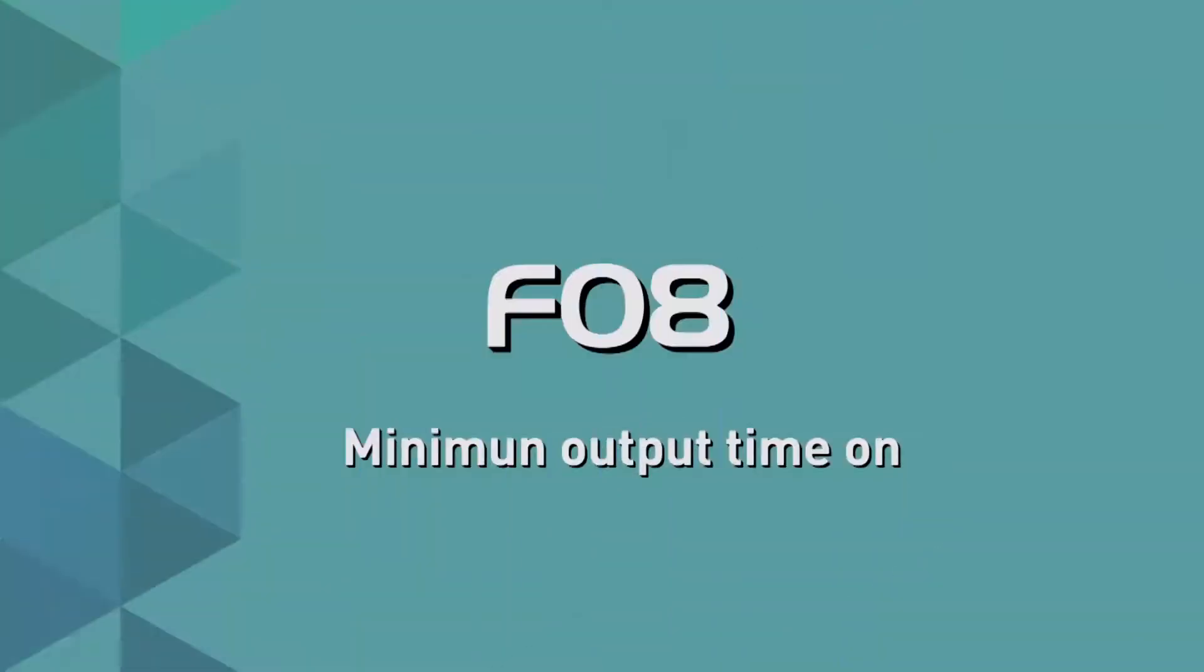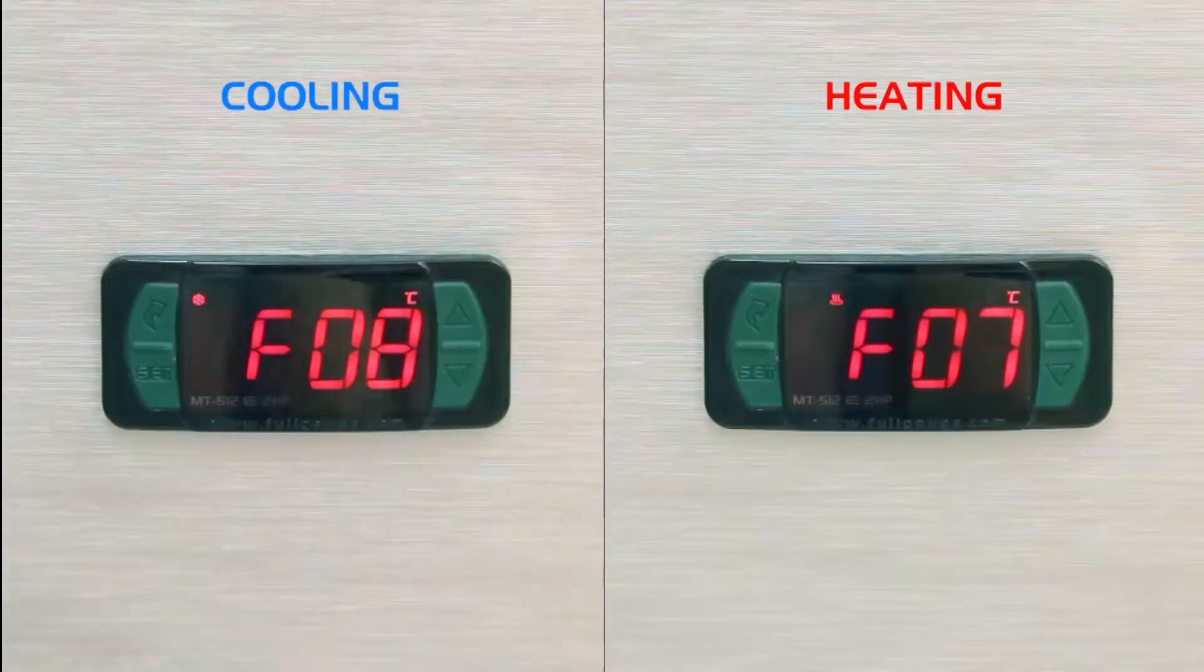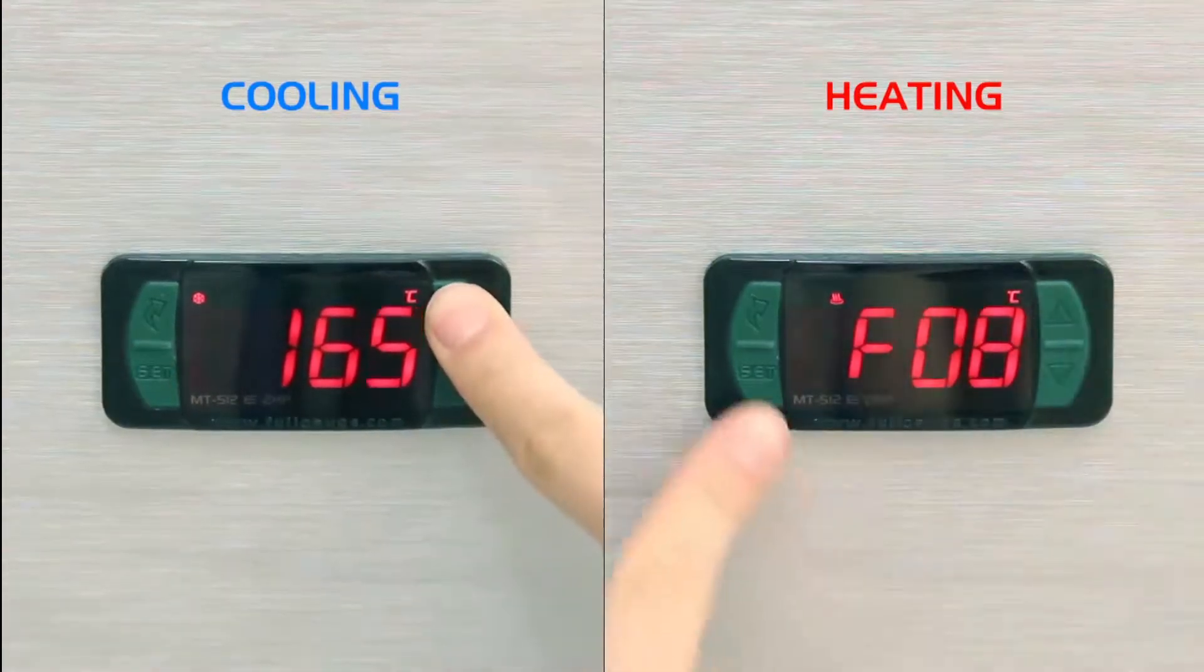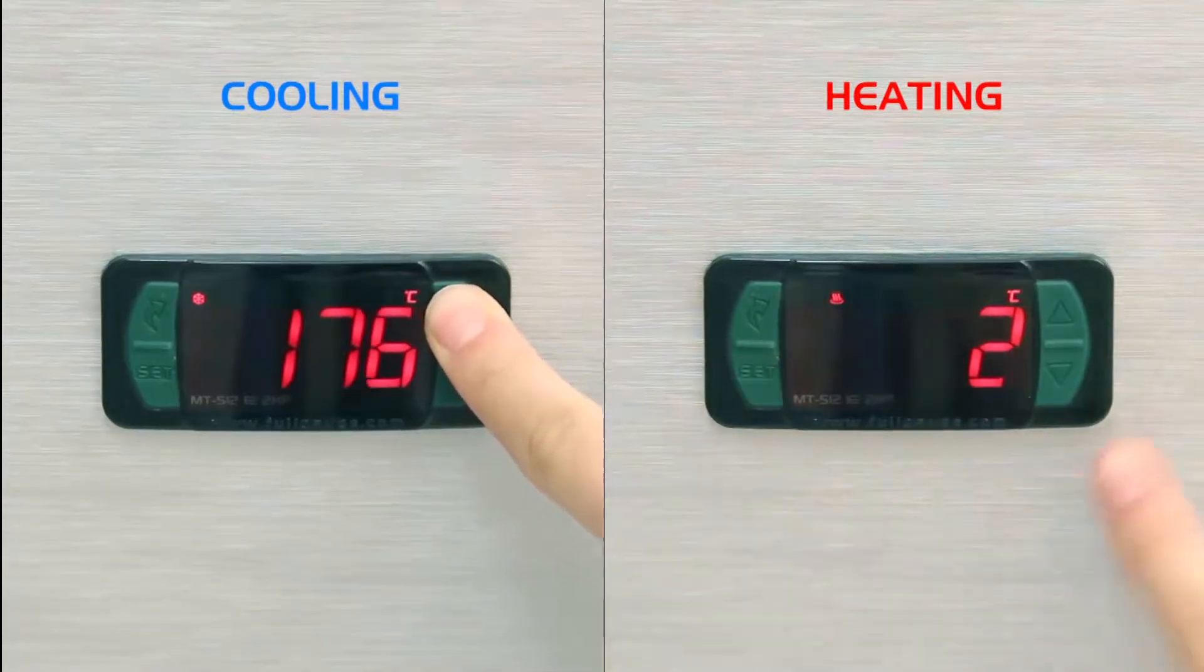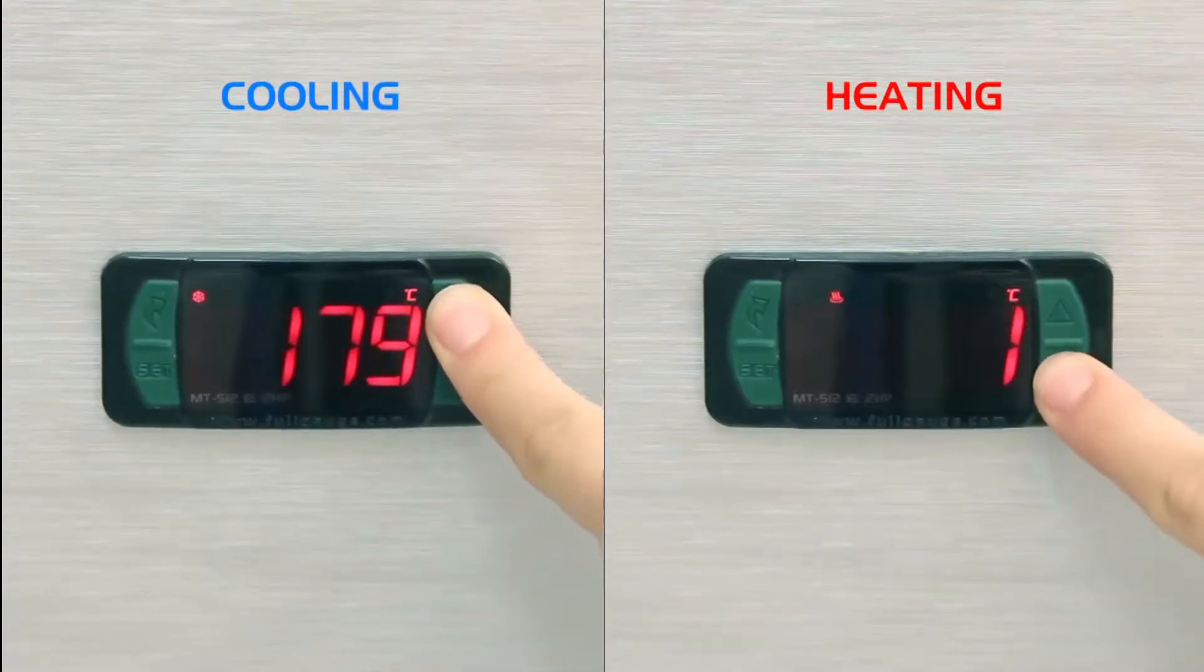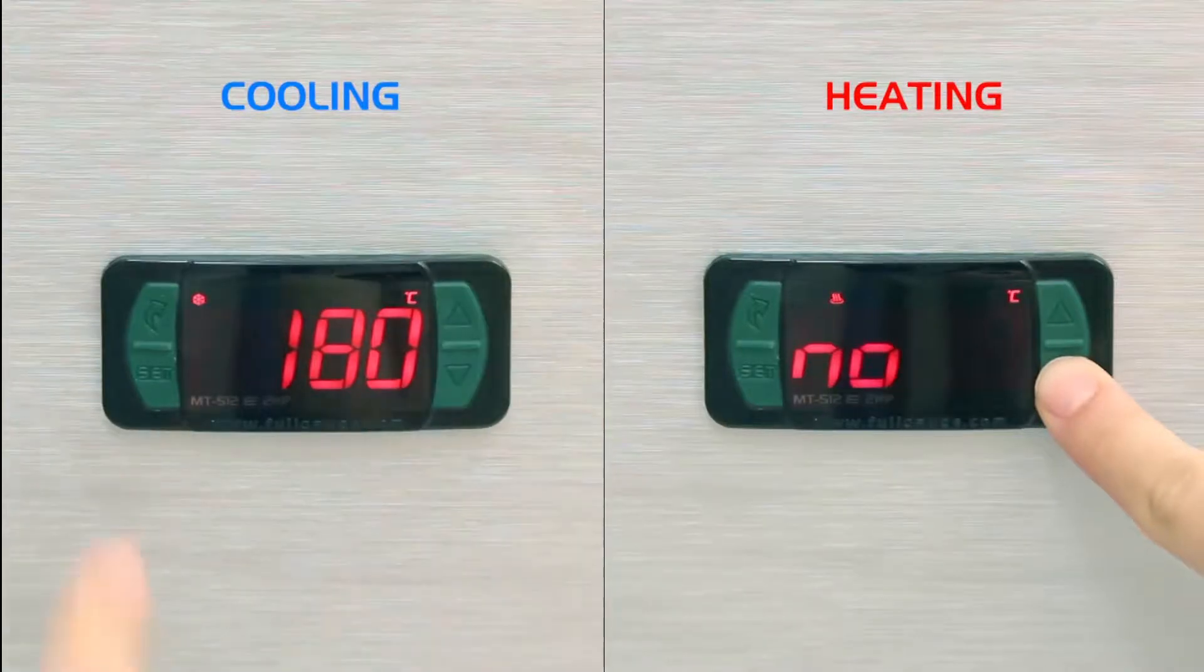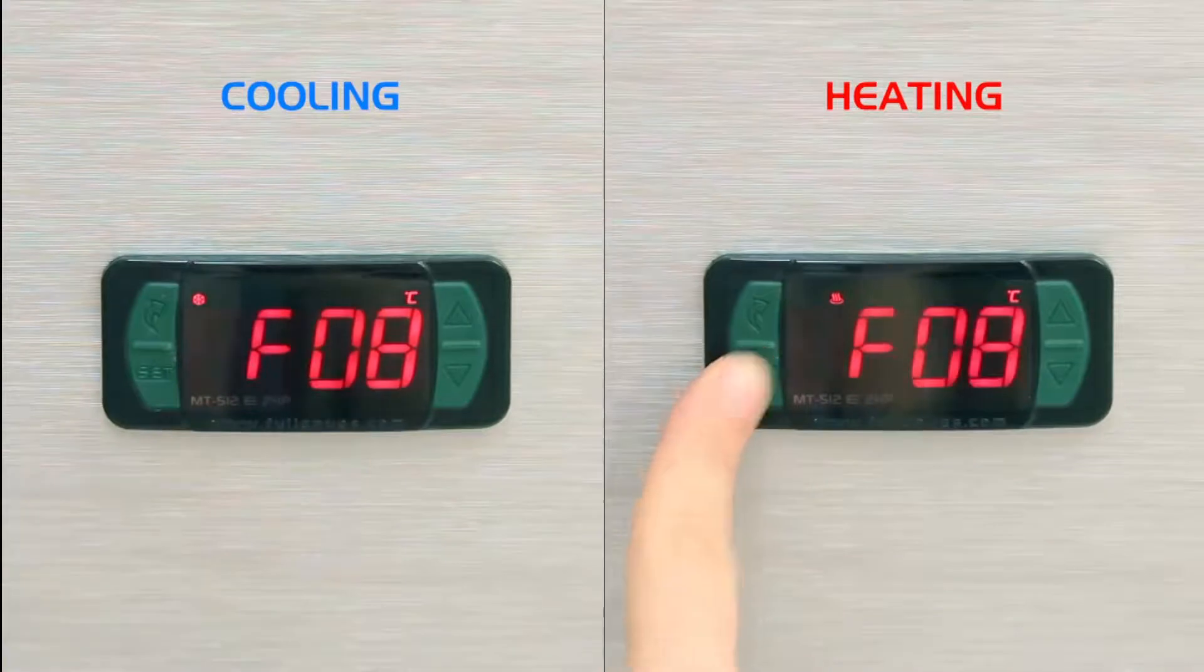F08 Minimum Output On Time: It is the minimum time in which the controller relay remains on after the last start. The goal is to avoid repetitive disconnections. In the cooling example, we opted for 180 seconds, and in the case of heating, we adopted no minimum time, selecting the No symbol.